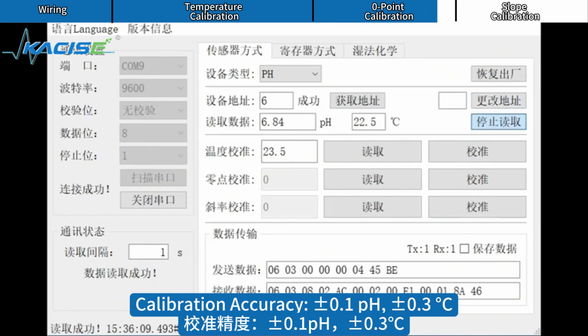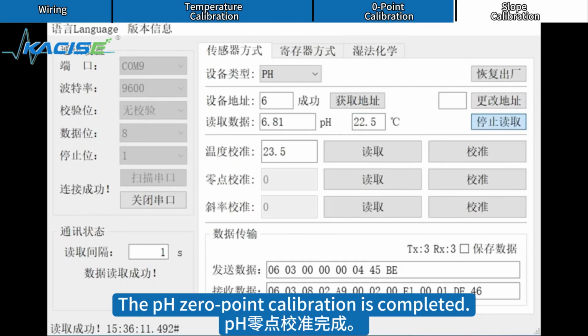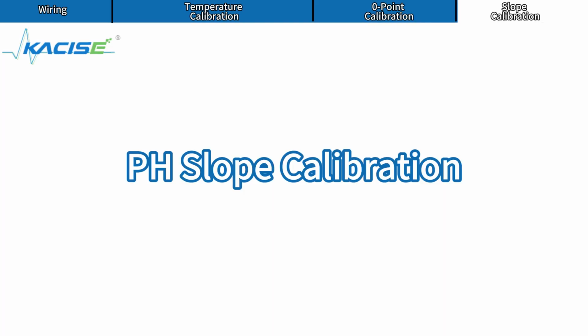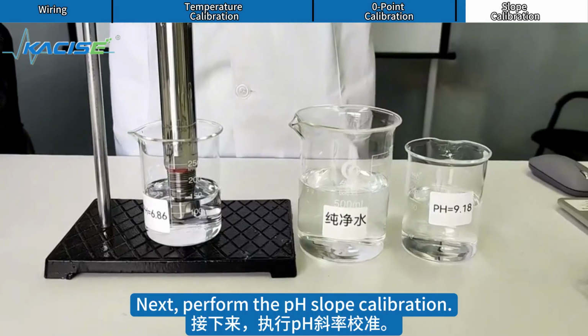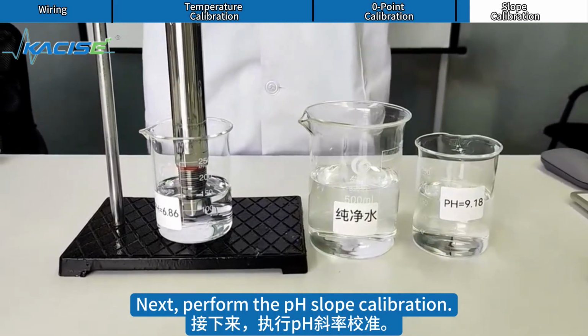Calibration accuracy, plus or minus 0.1 pH, plus or minus 0.3 degrees Celsius. The pH 0-point calibration is completed. Next, perform the pH slope calibration.